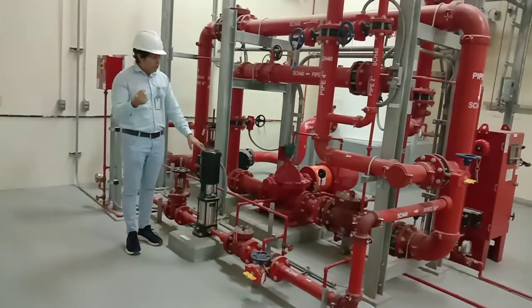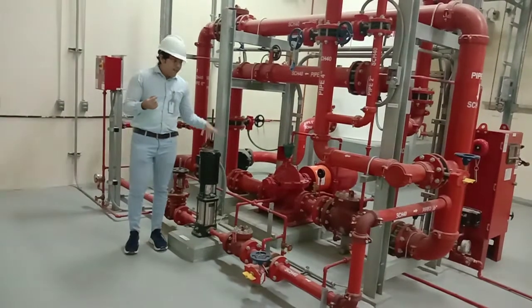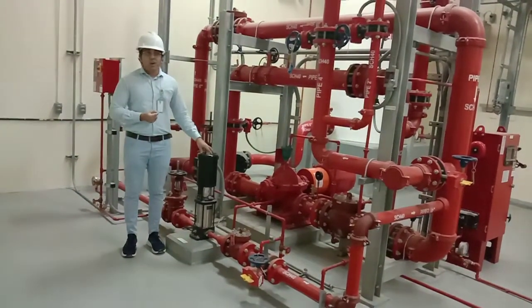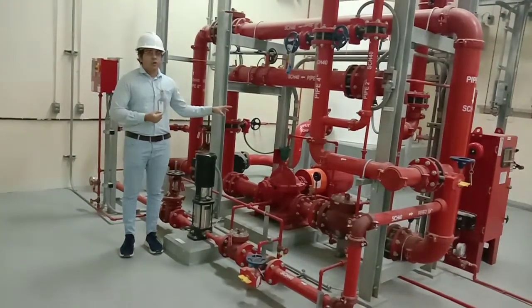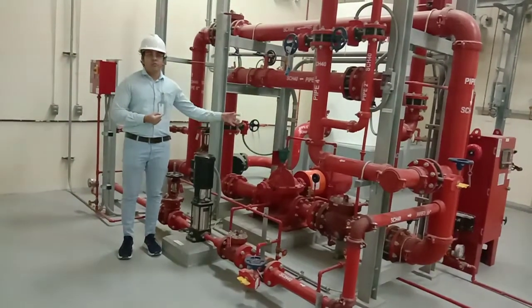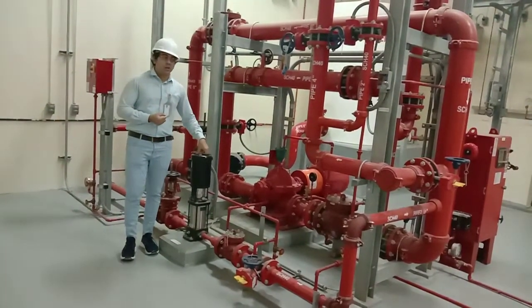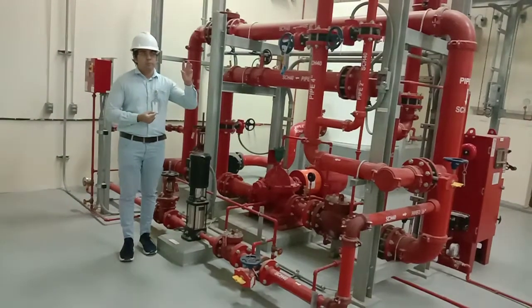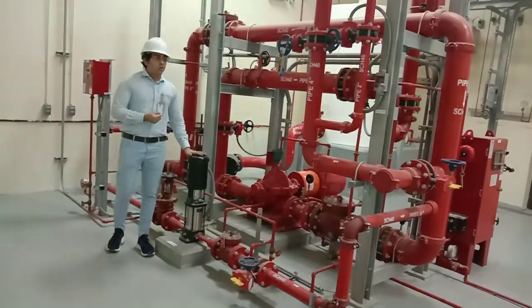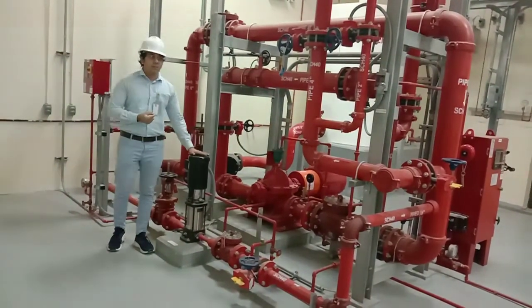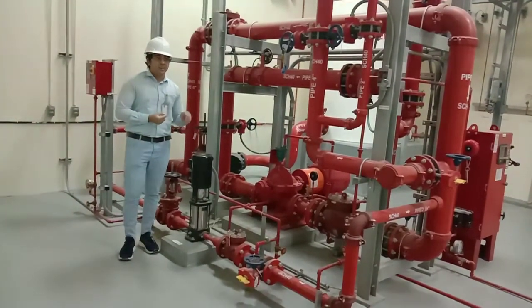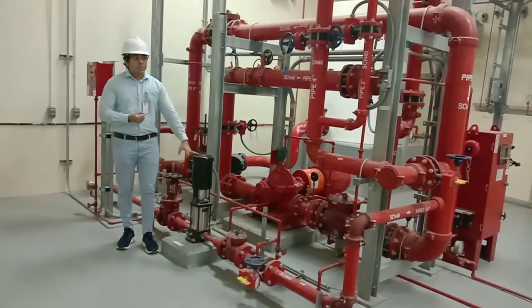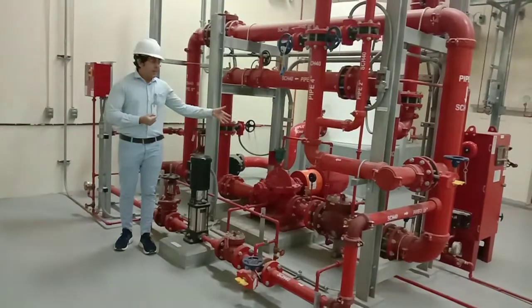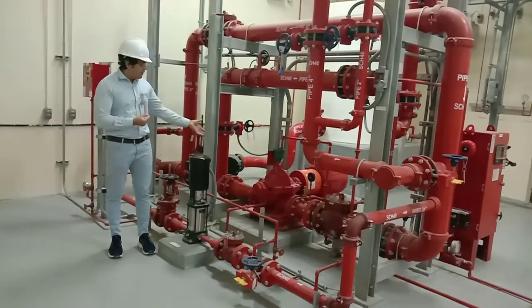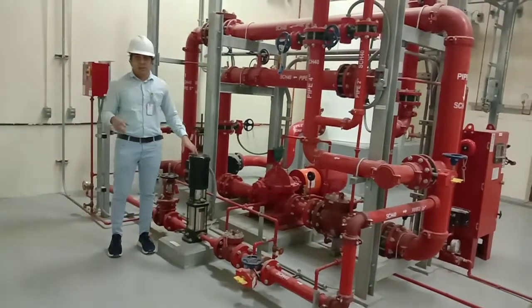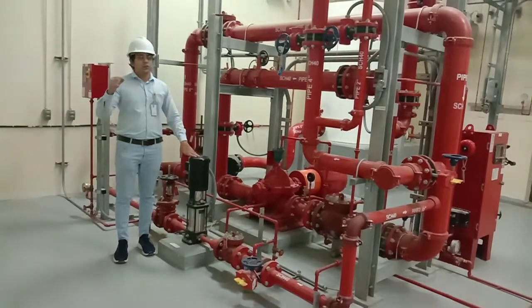Those leakages shall not be maintained by the main pump, because we don't want to start or stop the main pump very frequently to maintain those leakages, right? So those leakages should be maintained only by the jockey pump. Now, the idea behind that is the life of the main pump, right? The bearing, the shaft, the mechanical equipment, the impeller, everything. We don't want that to rotate frequently.